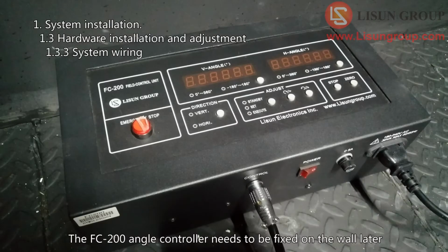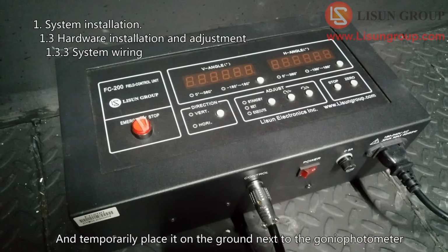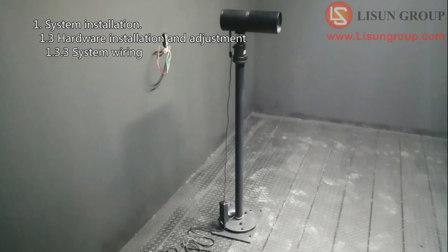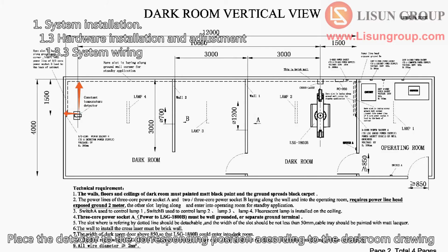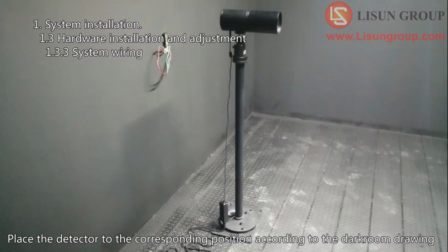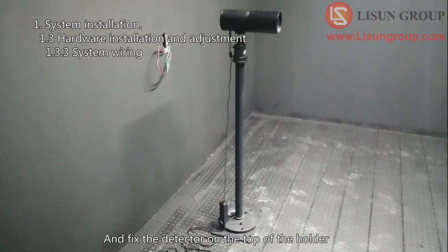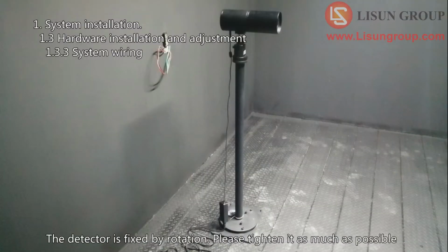The FC200 angle controller needs to be fixed on the wall later. And temporarily place it on the ground next to the goniophotometer. Assemble the detector holder and the detector. Place the detector to the corresponding position according to the darkroom drawing. And fix the detector on the top of the holder. The detector is fixed by rotation. Please tighten it as much as possible.